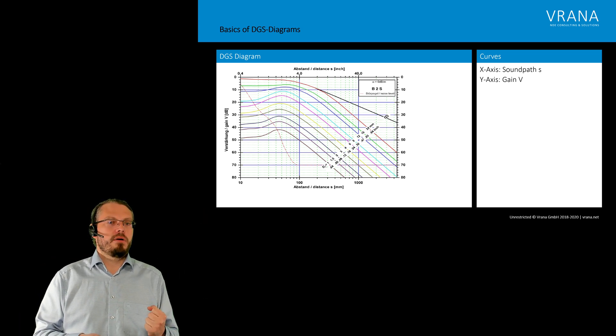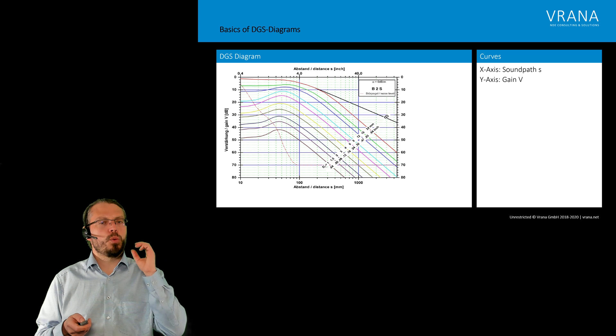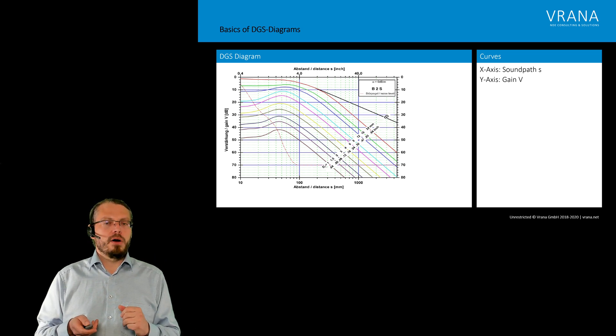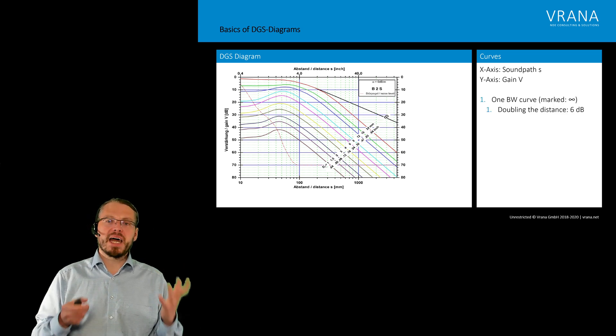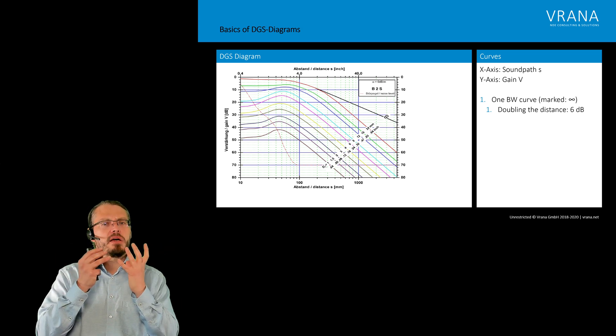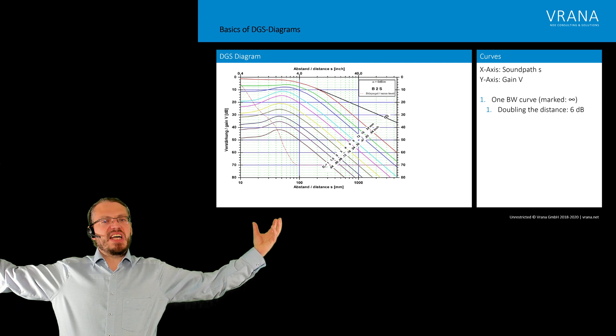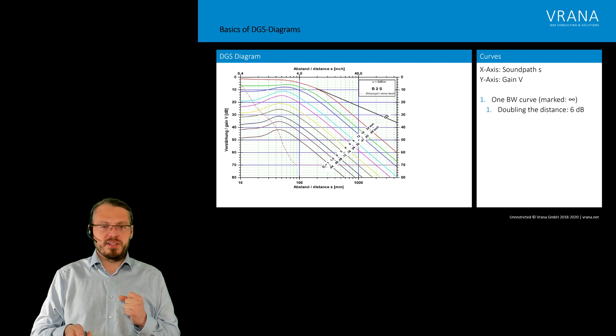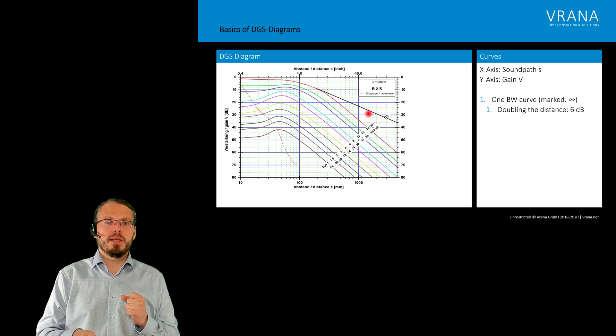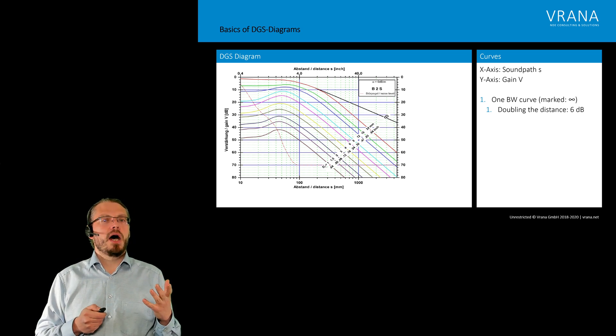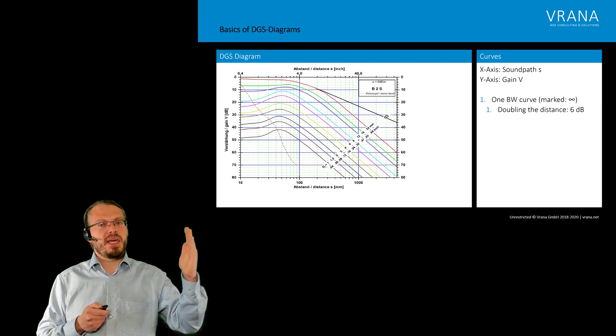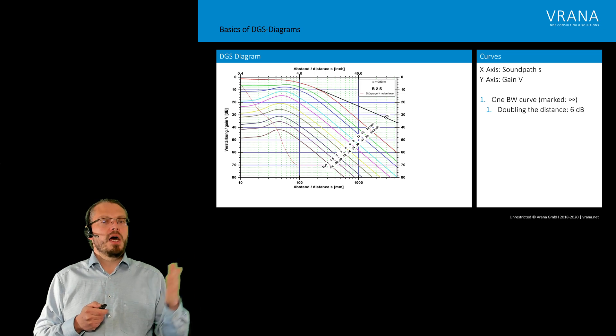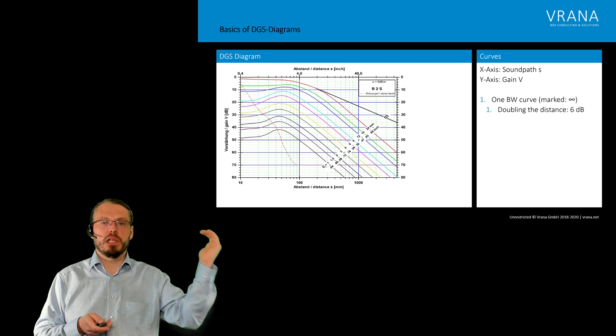On the other axis we have our gain, and we have a lot of curves in this diagram. The topmost curve is our so-called back wall curve. A back wall is an indication of infinite size, which is why this curve is marked with the infinity symbol. If we go to a sound path of 1000 mm we see about 23 dB, and at 2000 mm we see about 29 dB — a difference of 6 dB. So if we double our sound path on the back wall curve, we have to add 6 dB. That's the slope of the back wall curve.